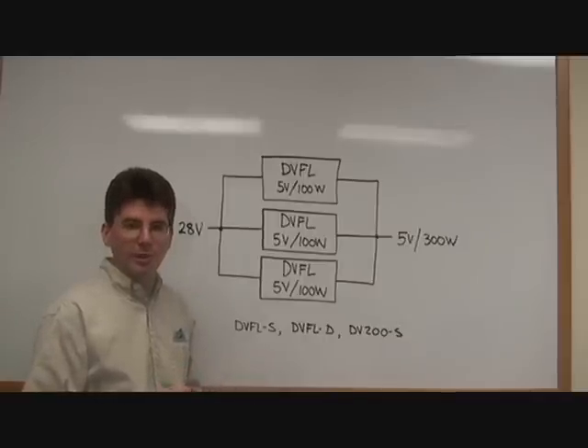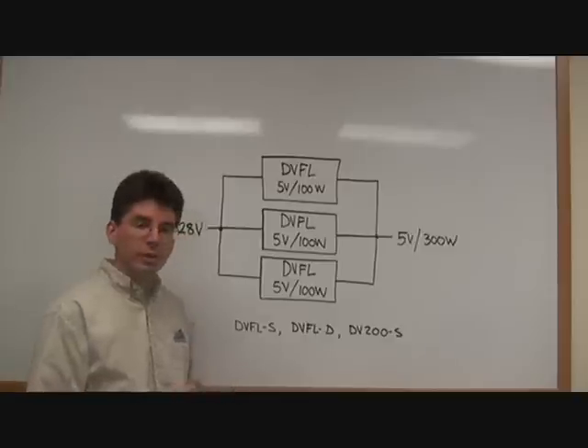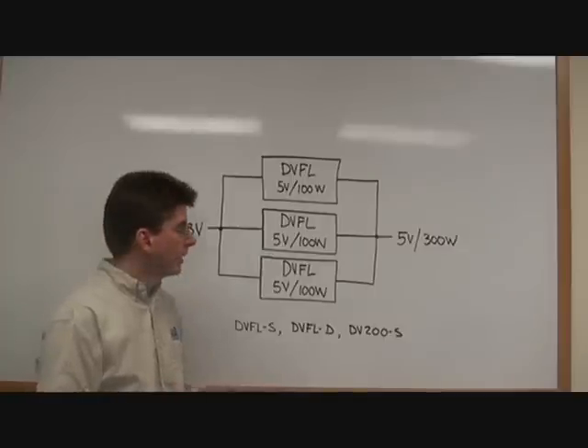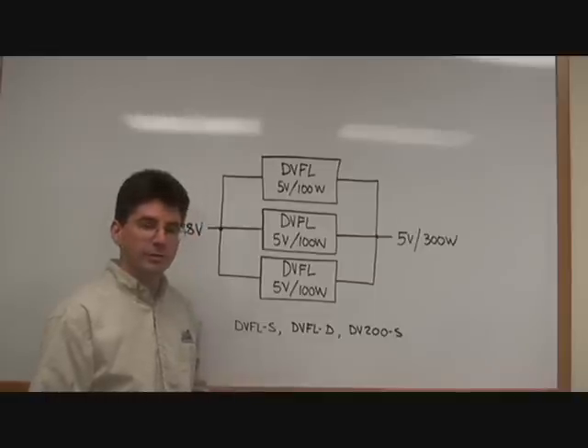It's important for reliability to prevent one converter from taking the entire load to spread the thermal and electrical stresses among the various DC-DC converters. In general, up to five DC-DC converters can be put in parallel.